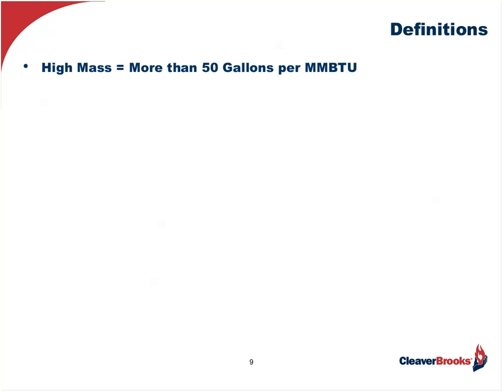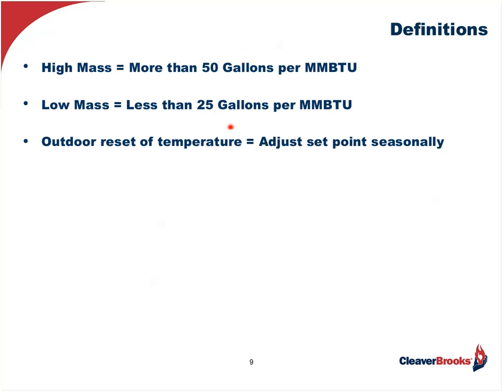Now, a few more terms that we're going to be talking about in this presentation. High mass. These are boilers that have more than 50 gallons per million BTUs. A low mass boiler, by contrast, only has 25 gallons per million BTUs, and in fact, some of them out there have less than 10 gallons per million BTUs. Outdoor air reset. I'll talk about that in the next slide, but essentially we're adjusting the set point seasonally, the set point of the hot water temperature.